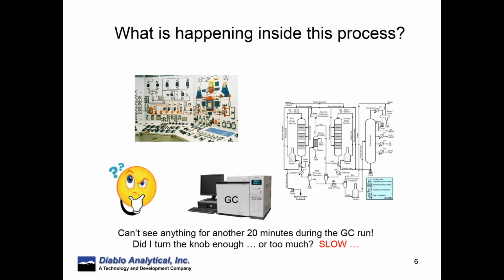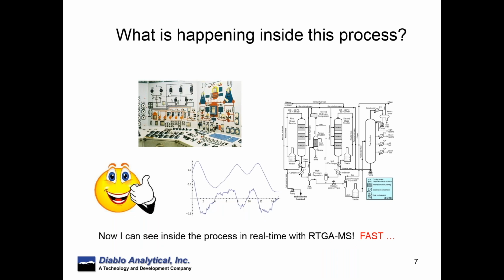So by today's standards, GC is considered slow and not real time. If you take an RTGA or a mass spec appropriately designed, now we can acquire data on the single second time frame. And so now, as you can see in the graph there, we can see in real time how various parameters and various chemical concentrations are changing within our process. And therefore, in real time, we get a video instead of a snapshot, and now we can more easily see what's happening and then possibly make changes in our process. So by modern standards, this is considered fast.